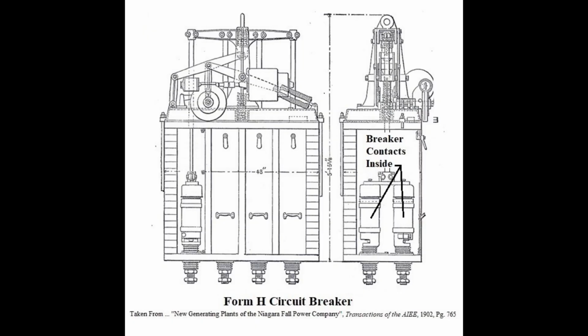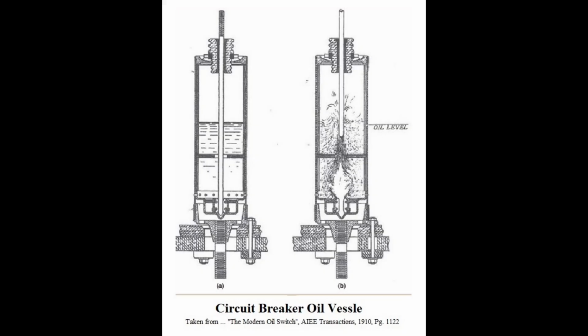Oil was, and in many cases still is, used in circuit breakers today. When contacts are separated under heavy electrical faults, the extreme heat of the arc vaporizes the mineral oil. On the left is an oil vessel with a completed circuit. On the right, the contacts have just begun to separate to produce a high-pressure bubble of hydrogen gas. This gas was intended to cool and deionize the arc in order to stop the current flow.